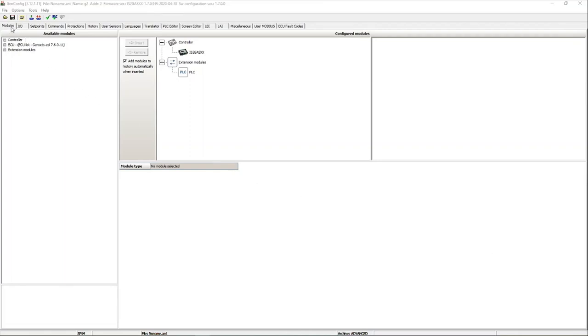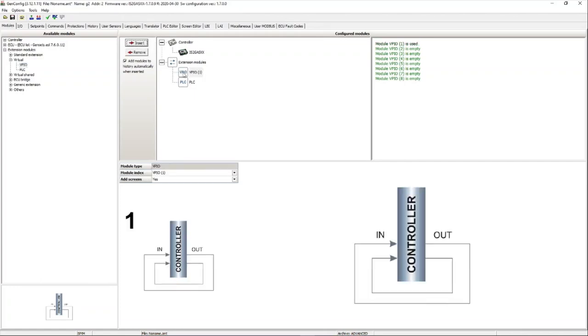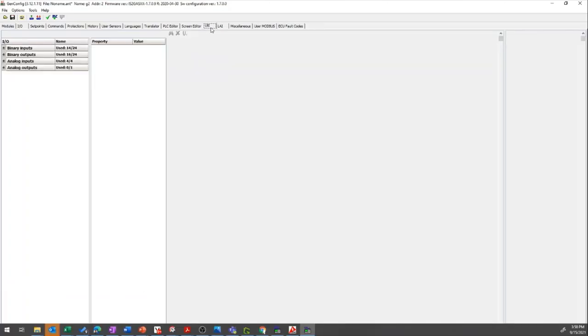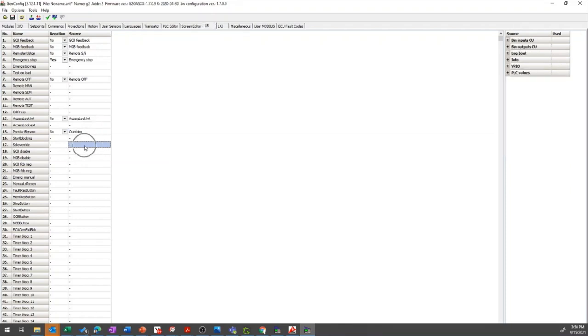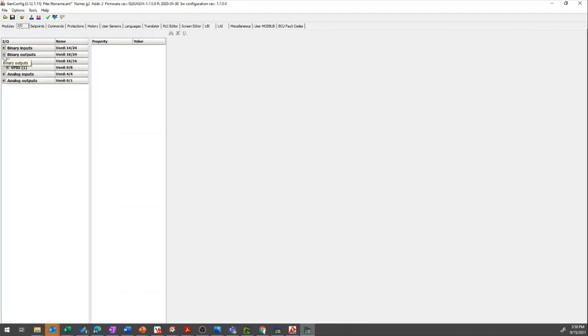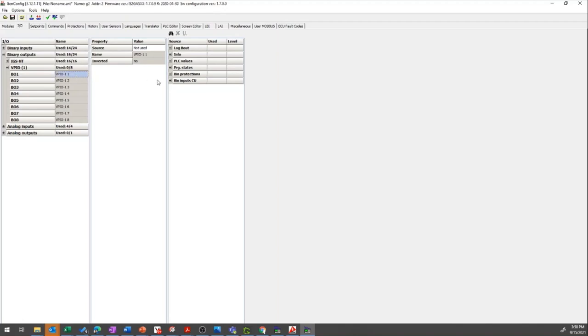Let's go with the following difference with Intelligent NT controllers, which has to do with the VPIO modules, which means Virtual Peripheral Input-Output. The VPIO in the Intelligent NT controllers are virtual extension modules and are used to connect LBOs or logic binary output functions to activate logic binary input functions or LBIs. If we try to assign the value to an LBI, we only have available the binary inputs and outputs, logic binary outputs, input, VPIO and PLC group, but we don't have an important group that is the program states. While the VPIO outputs can be assigned variables of these groups, plus the program states, to then be used as binary inputs in the controller.